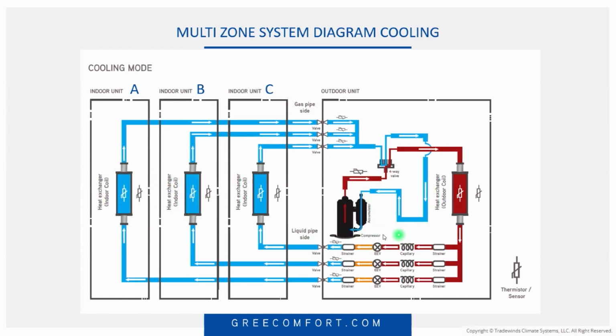So what you're going to see when you have a system that's low on refrigerant is elevated discharge temperature. Now, if you have the service tool, which we're going to talk about very shortly, you can see that discharge temperature, and you would see that it is quite elevated. But let's say you don't. You don't have to have the tool. Let's say I run this unit, and I've got enough refrigerant in it that I can satisfy one, but I can't satisfy all three. So if I go across and I've got all three, and I've got, let's say, a 15 degree TD, a 10 degree TD, and maybe a 12 degree TD, but then I shut off circuits B and C and only leave A on, and all of a sudden that jumps up to a 20 degree TD.